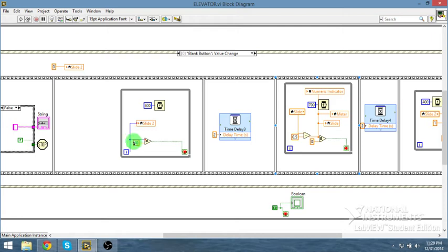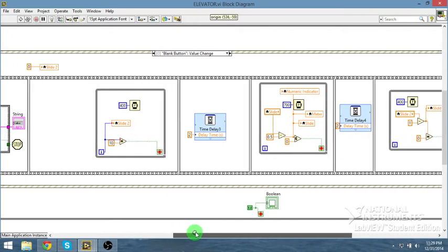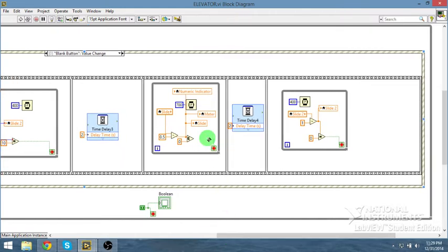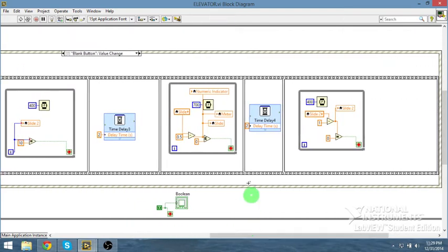So with those numbers, I can run this loop, adding 1 every time the loop goes around. Basically the whole loop will run through once a second. So that door will close with a 400 millisecond timer on it until it reaches x equals y, which is 10, and then that part of the program will stop. And then here's another safety input. There's a 2-second time delay before the elevator starts to move. And then, you hit the ground floor, so it's going to go to the ground floor.